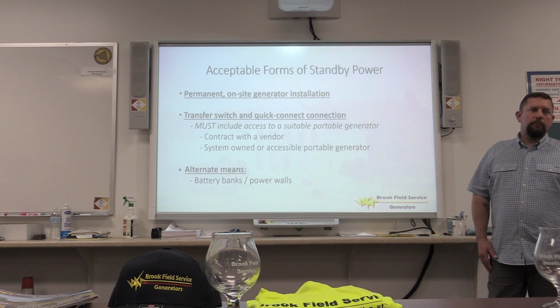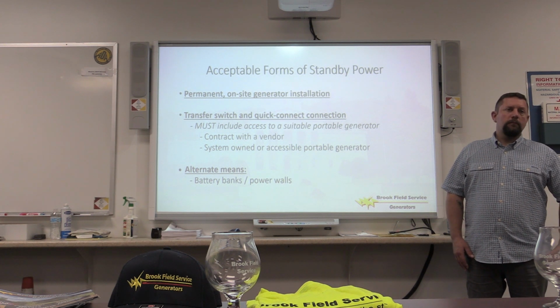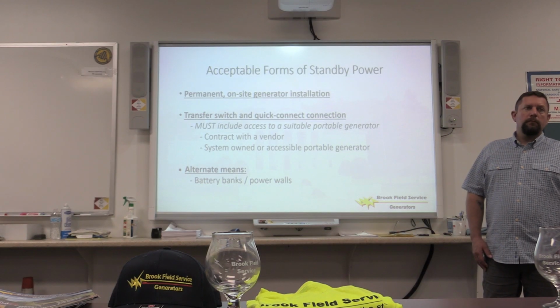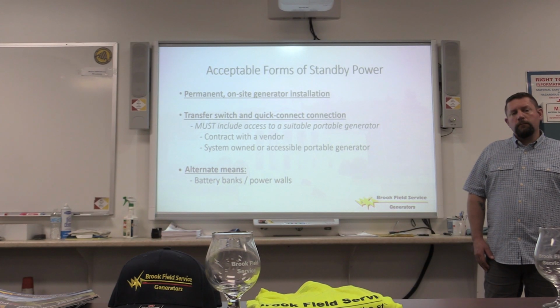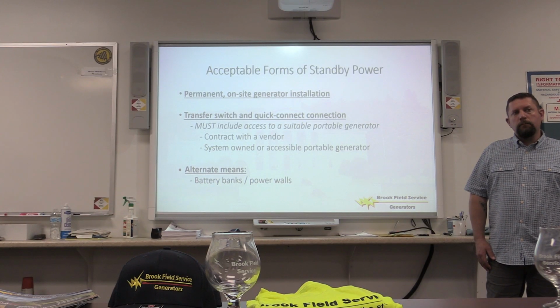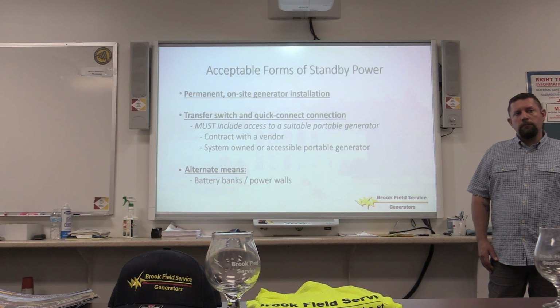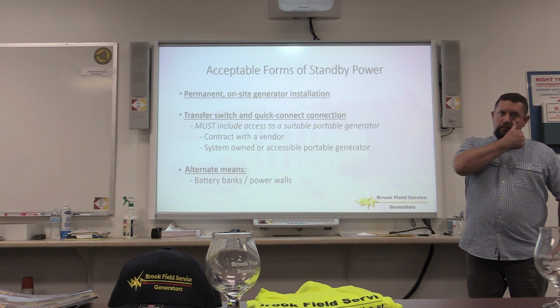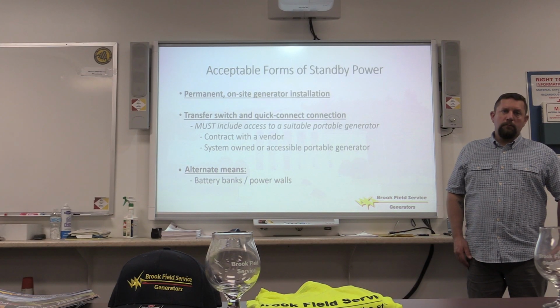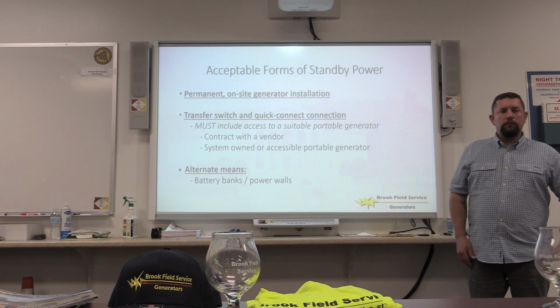The one thing about the smaller booster stations, many of them, we're doing one in Williamstown. We've done Barre, a number of them. Typically the pumps are smaller, and you can use an air-cooled generator, and it's usually very simple to set up. You're talking about $8,000 for that pump station, and when you start doing the math about running a towable around various stations, particularly if there's bad weather or roads are flooded, that can be an impediment to even getting the towable to the location. So in those small booster pump stations, the air-cooled units go up to 26 kW, which gives you roughly 110 amps, and most of those small booster pump systems are 100 amp, single phase. So they may be a good alternative, and over the long term a much better solution.